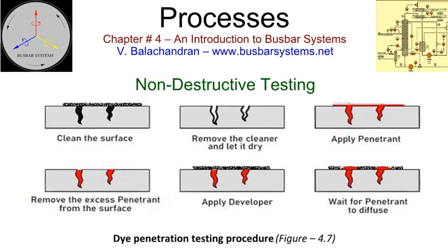Dye penetrant test. Dye penetrant test is also referred to as liquid penetrant test, LPT. This test can only detect the surface breaking discontinuities or hairline cracks on the surface. Any discontinuity that is embedded inside the weld cannot be detected by this method. It is also not suitable for porous or rough surfaces where the interpretation of the test result could be misleading. It cannot detect a lack of fusion in a weld. It is one of the most prevalent methods of testing in the bus industry and can be used for weld inspection of ferrous as well as non-ferrous material.